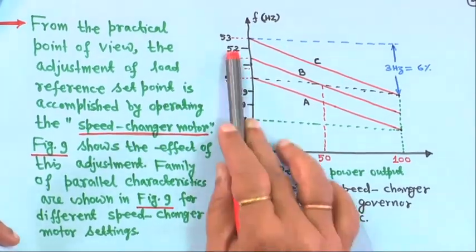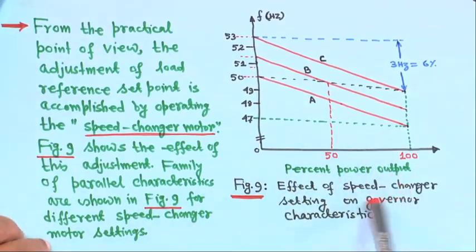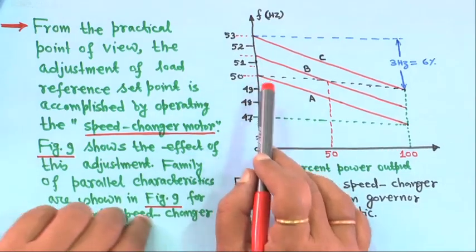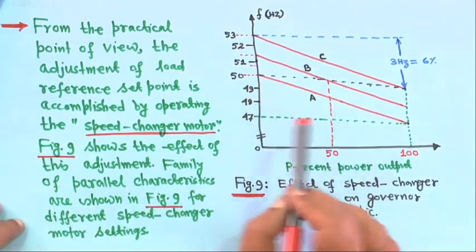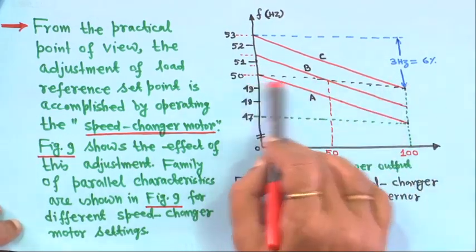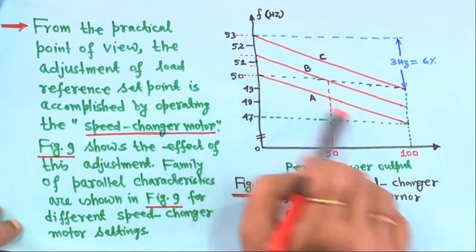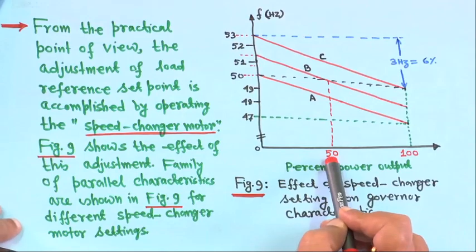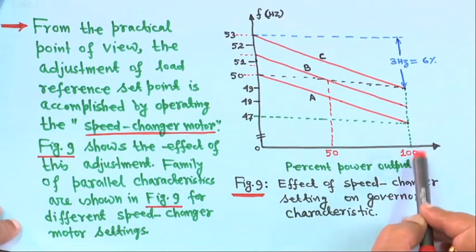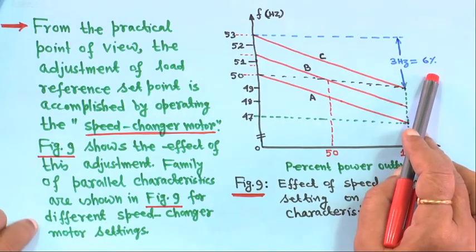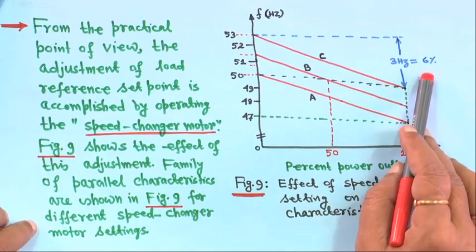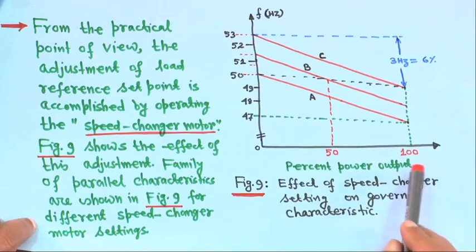The vertical axis is frequency in hertz, showing the effect of speed changer setting on governor characteristics. At 50 hertz, for characteristic A the generation is 0, because drawing a horizontal line at 50 hertz starts from A. For B it is 50 percent, and for C it is 100 percent. A 3 hertz change equals 6 percent in a 50 hertz system, so 1 hertz equals approximately 2 percent of power output.